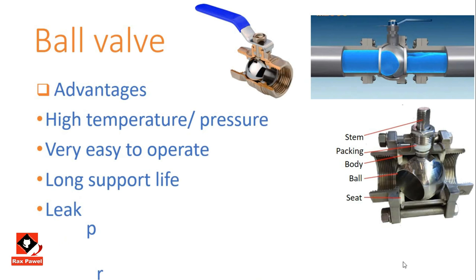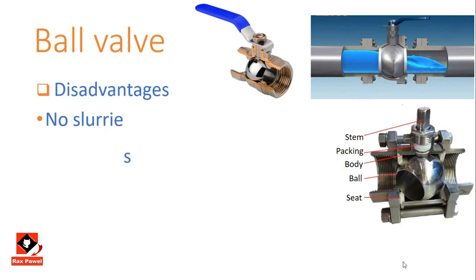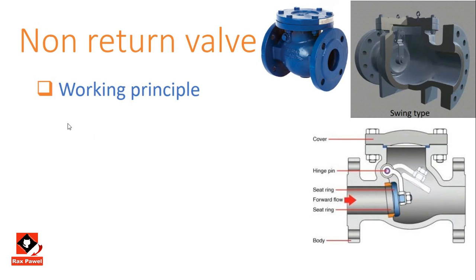Disadvantages of the ball valve: it is not suitable for slurries, as solid matter can damage the sealing surface due to dead space, and it requires proper maintenance. Working principles of the non-return valve, also known as the check valve: its function is to prevent backflow by means of a moving seating ring. It allows flow in only one direction and is usually essential after a pump, working automatically such as during a power cut. There are three types: swing, dual, and lift.